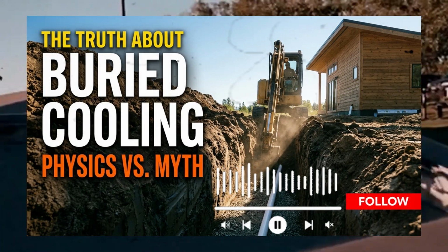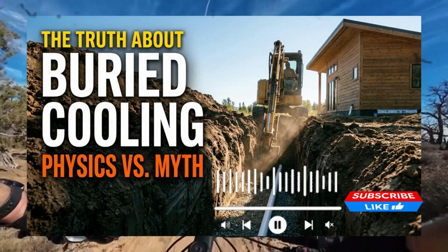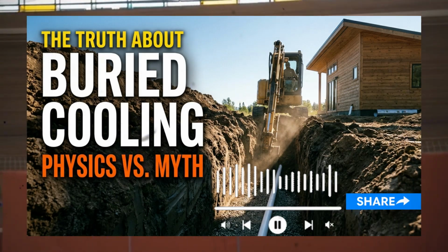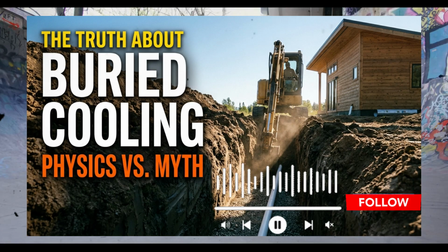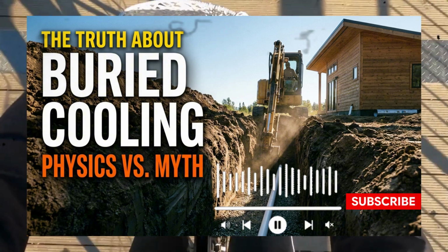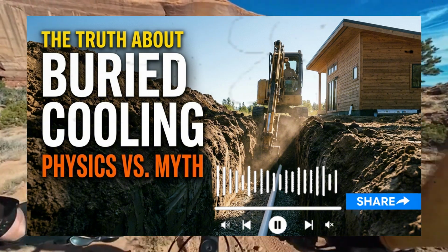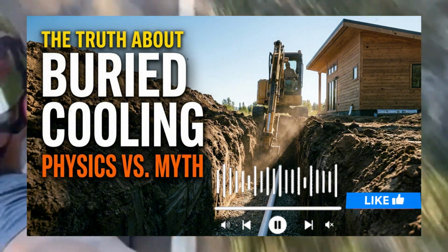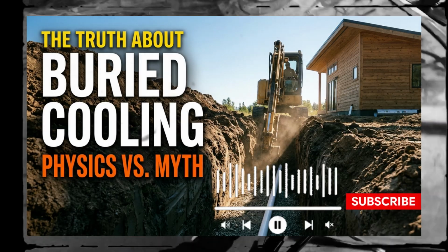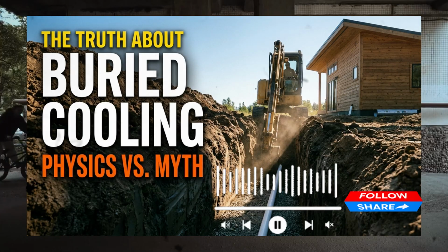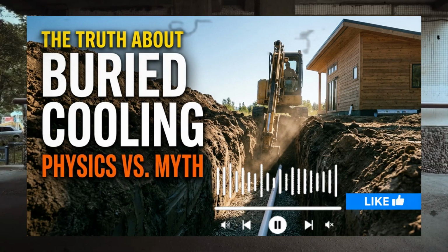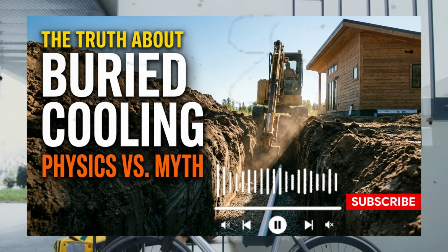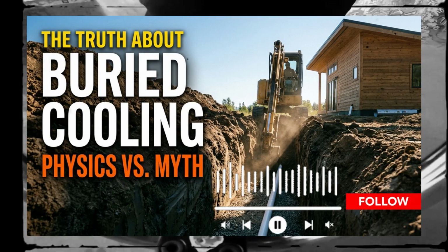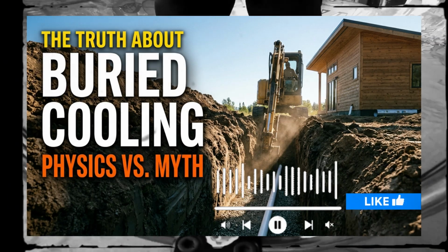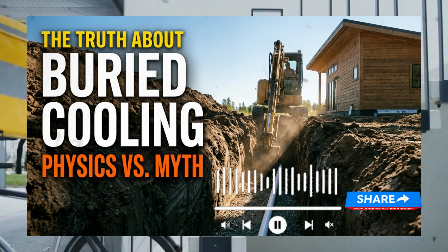By the time you reach a depth of 6 to 8 feet, the soil no longer reacts to the daily sun or passing cold fronts. Instead, it responds to the average temperature of the entire year. This creates a seasonal lag, a physical delay of several weeks or even months. At a depth of 6 feet, the thermal lag is typically 6 to 8 weeks. At 8 feet deep, that delay stretches to nearly 12 weeks, a full 3 months.